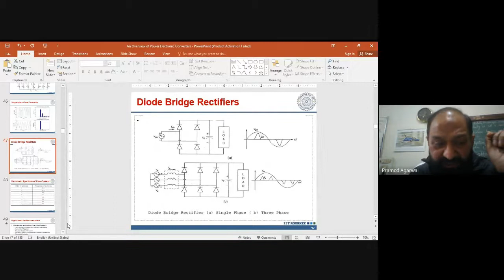Similarly, in this case, when the line-to-line voltage exceeds the capacitor voltage, then the current is drawn. So there are 2 current pulses in both half cycles. These current pulses have a dominant third harmonic; it is peaky in nature. If you see the spectrum, you have a third harmonic of 73.5%, and all odd order harmonics are present.